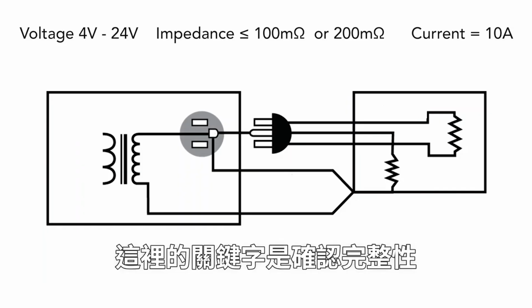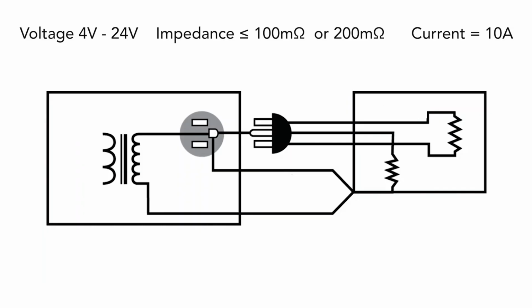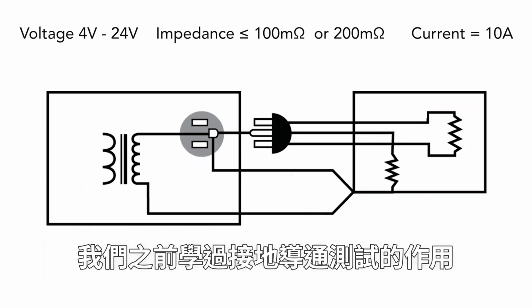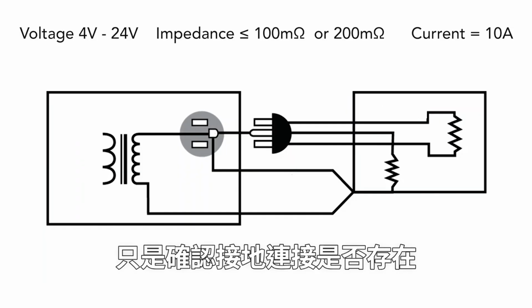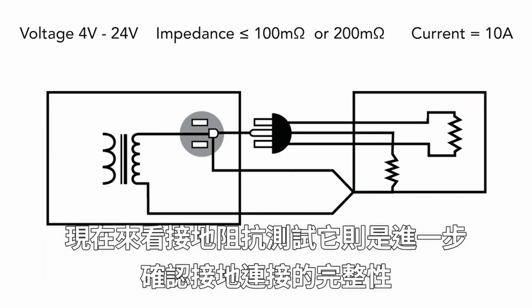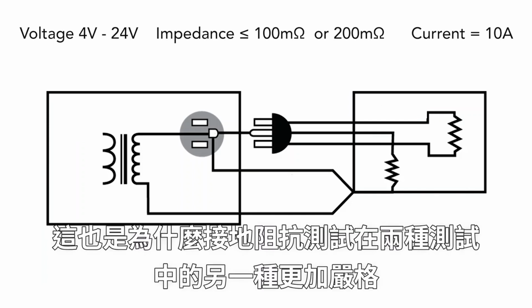Now the key word here is verifies the integrity. Remember that earlier we learned what the ground continuity test does, that it only verifies that a continuous ground connection exists. Now looking at the ground bond test, it verifies the integrity, which is what makes the ground bond test the more stringent of the two.